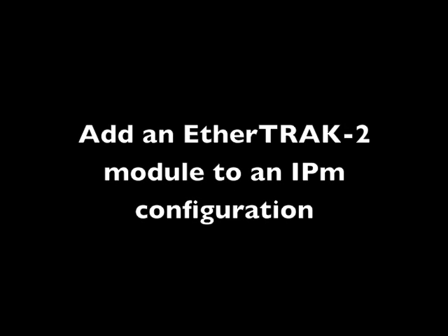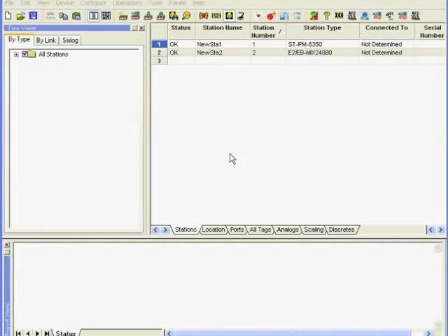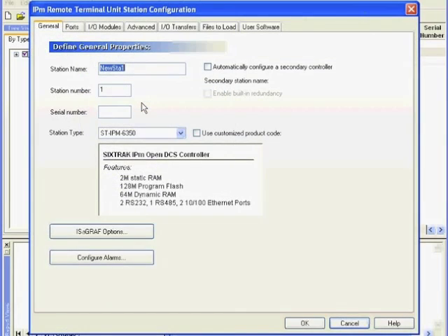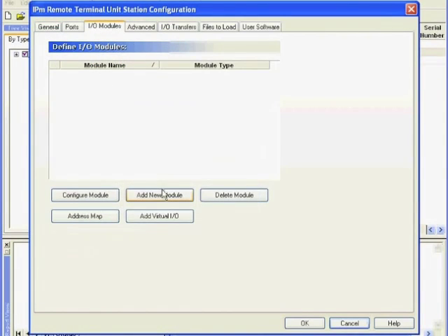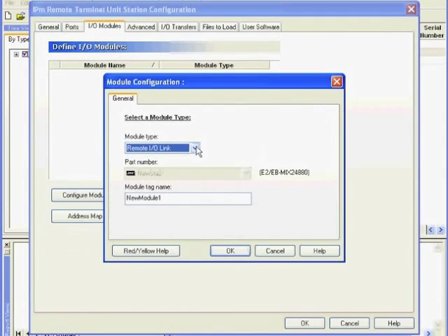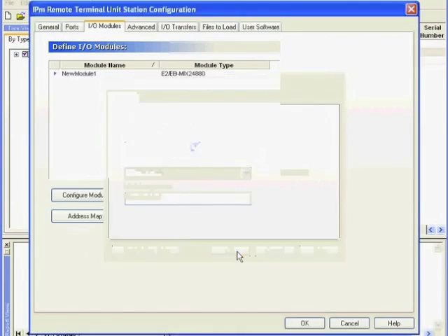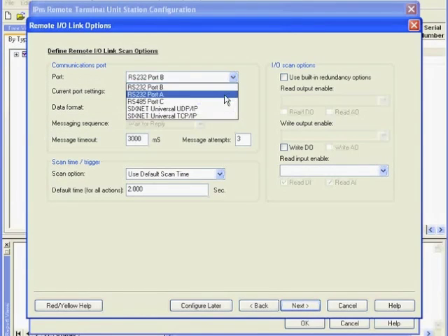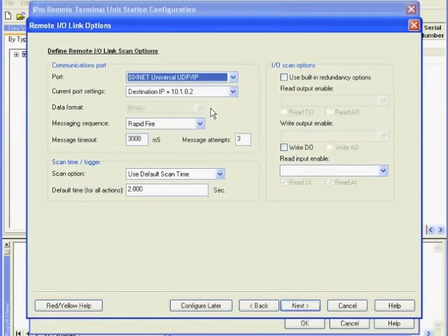Adding EtherTRAK-2 to a SIXNET RTU is easy. Simply add the EtherTRAK-2 module to the project file, configuring the I/O address and station number. Then go into the I/O module configuration of the IPM and click the Add New Module button. Select Remote I/O link from the Module Type drop-down and your module will appear. Click OK to go through the Remote I/O link setup wizard and select the options that pertain to your configuration.